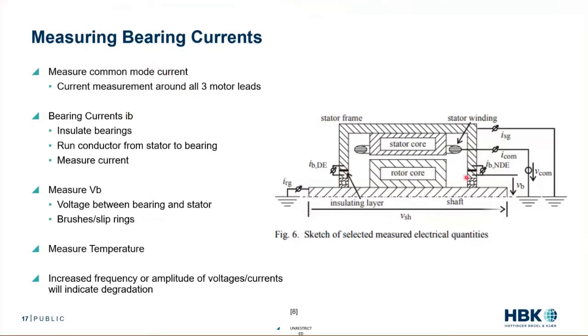We can measure the bearing currents IB. So if this is my bearing, you can see this little black dash here. I can put an isolation, electrical isolation, between my bearing and my housing. I can put a conductor from my bearing to measurement or to ground and then measure that current. I can measure that bearing current.